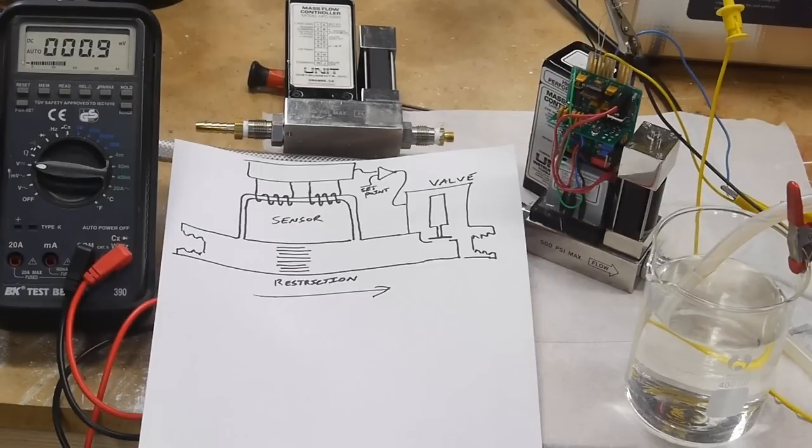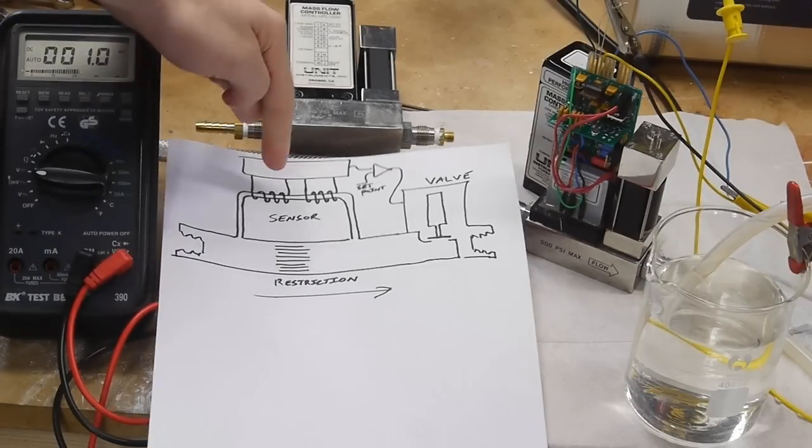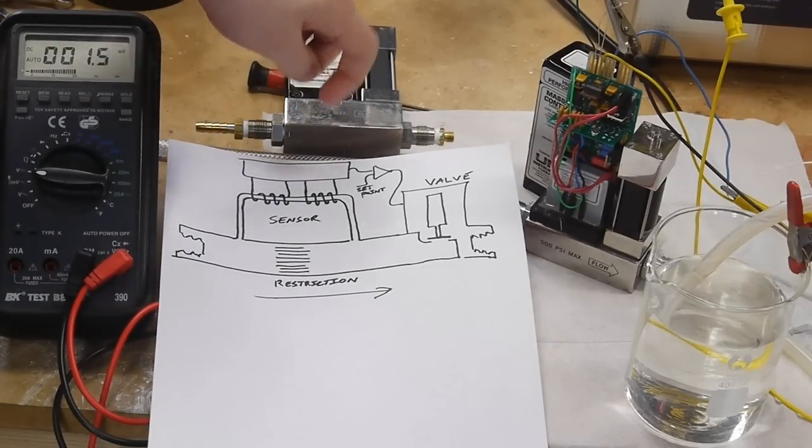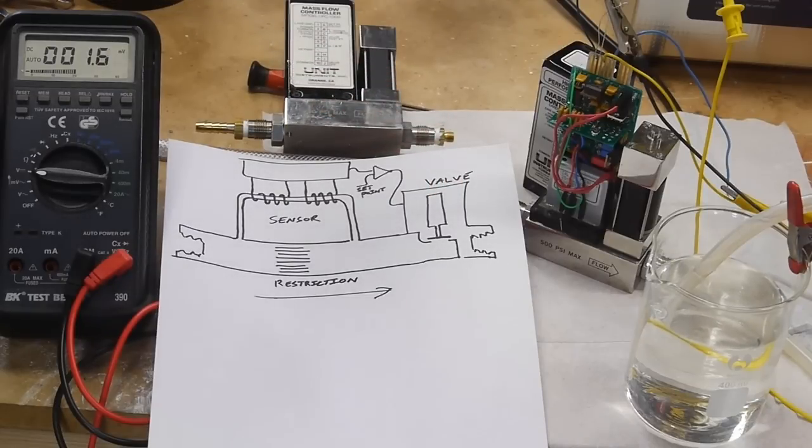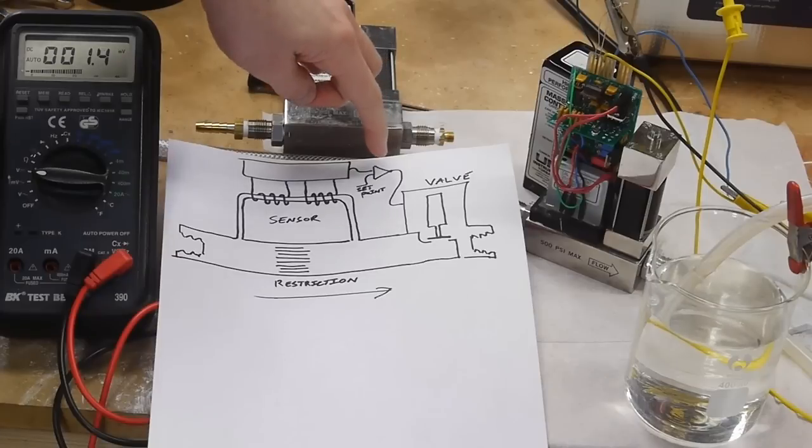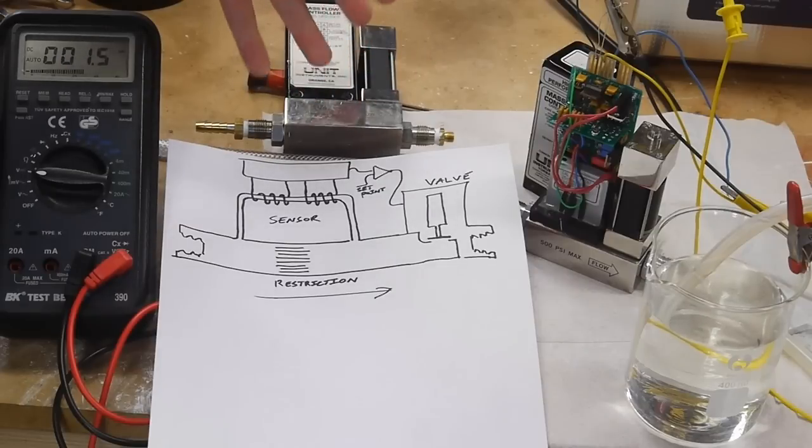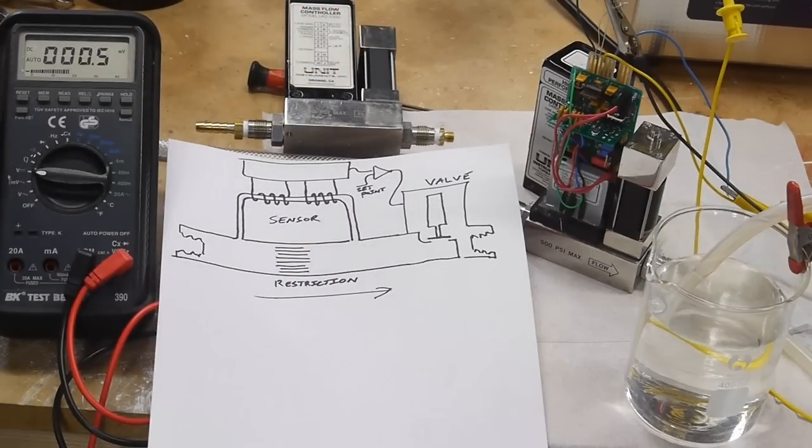The flow controller is an active device and it consists of a sensor and some analog amplification circuitry and a valve to regulate the flow of gas going through the whole thing. So the set point is determined by an external voltage and then that's fed into this analog circuitry so we basically have a closed loop servo control system.